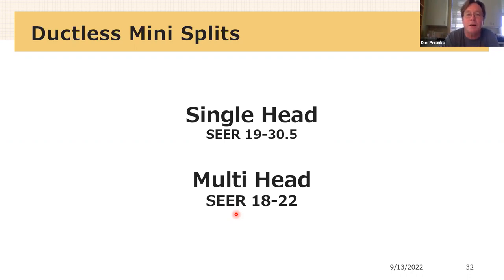But there's an efficiency consequence to the multi-head machine, right? Single head SEER goes from 19 to 30, multi-head SEER goes from 18 to 22. If you have a customer that's pursuing the higher SEER, that's pursuing an energy efficient building, you'd want to pick the higher SEER machine.